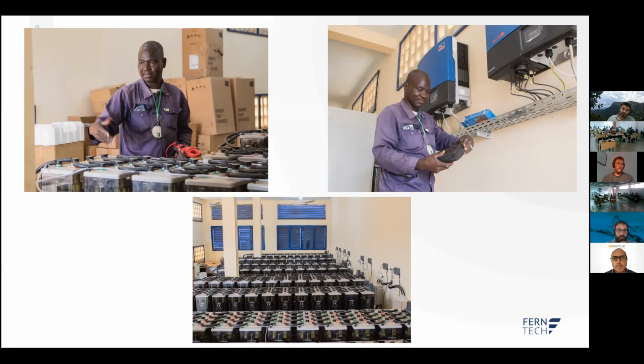The battery room looks pretty good, clean and tight, with some proper ventilation, but it's huge. So we have to take this into account too. If you were using lithium batteries, maybe because of the high specific energy, you can reduce the battery room size. You probably don't need as high ceilings as this one for proper ventilation, and you're also reducing cabling costs because you don't have as many battery banks as here. So it's all part of the process when designing the battery bank and the whole complete system.